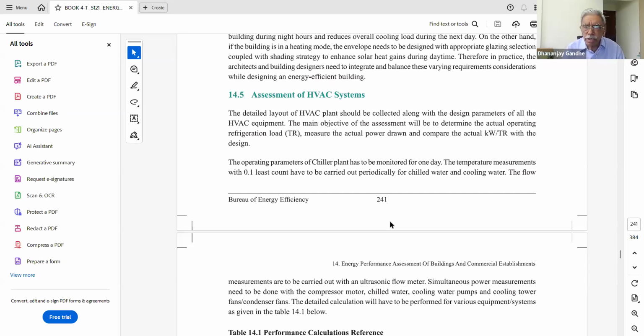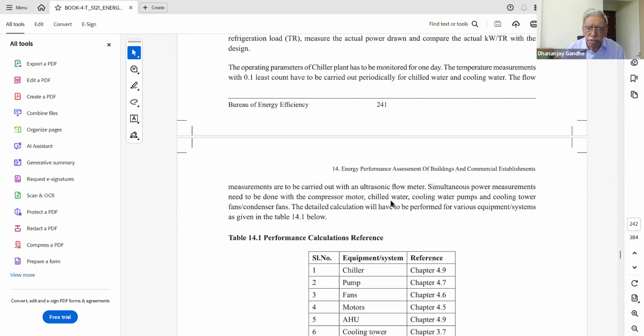The main objective of the assessment of the HVAC system is to find out the existing load on the HVAC system, in kilowatt or tons of refrigeration, and the actual kilowatt load that we can measure, and the ratio of the actual load that we measure over the refrigeration load in terms of tons. Refrigeration load means the cooling load. This ratio is to be compared with the design value to find out whether the air conditioning system provided is functioning properly or not.